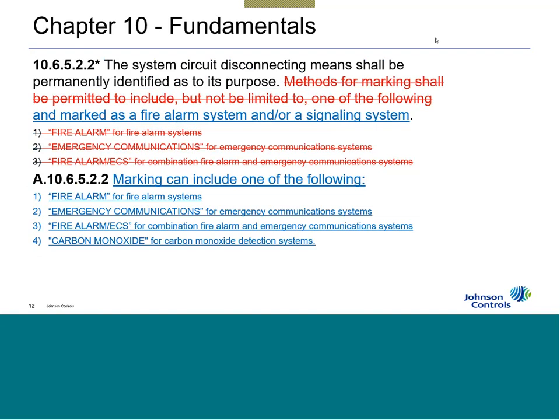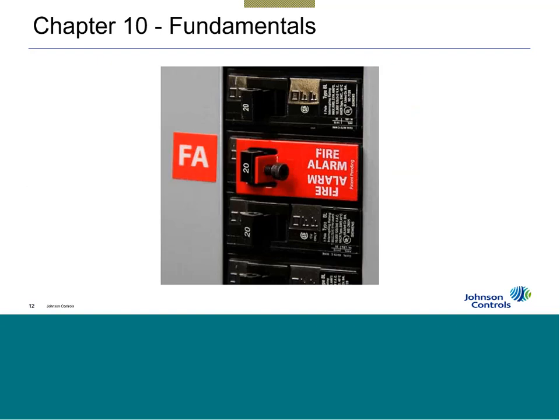Another one that I see has been modified a little bit over the years, but I see people, again, not adhering to the code. The disconnecting means, the circuit breaker, the power that goes to our control units, whether it's a 4009, a DAC, or whatever it is, we need to make sure that it's marked for fire alarm or mass notification use. This is what the code's looking for. Our partners at Space Age have these generic plates that can go over top of pretty much all the circuit breakers used in the U.S. I think they should be in your price book if you look under Space Age.